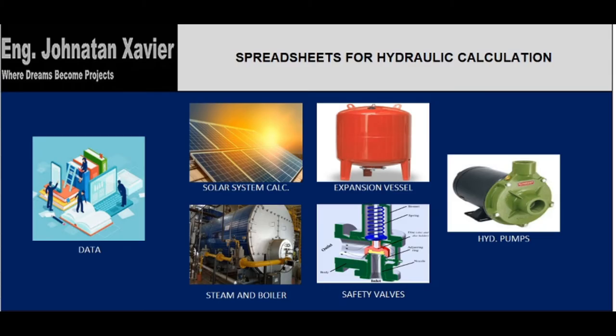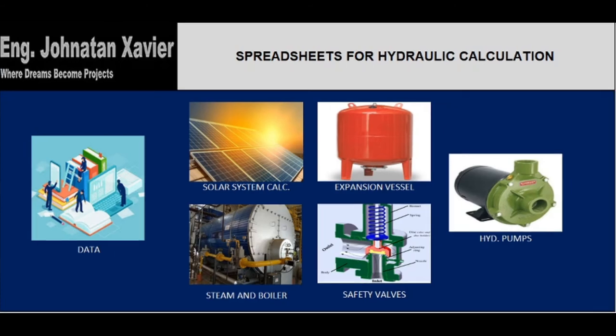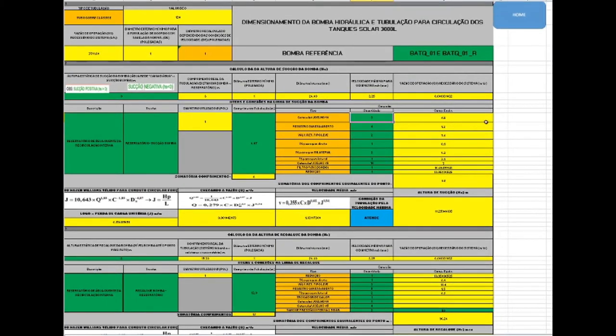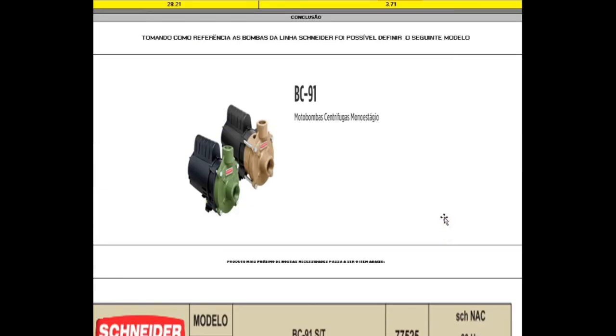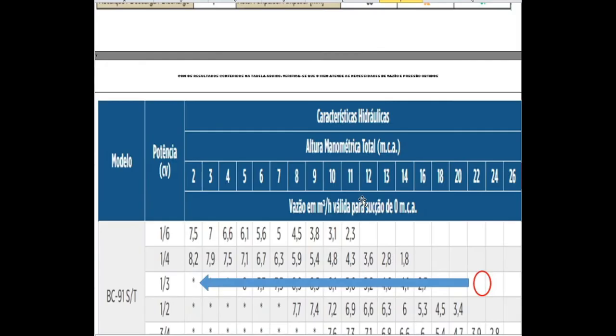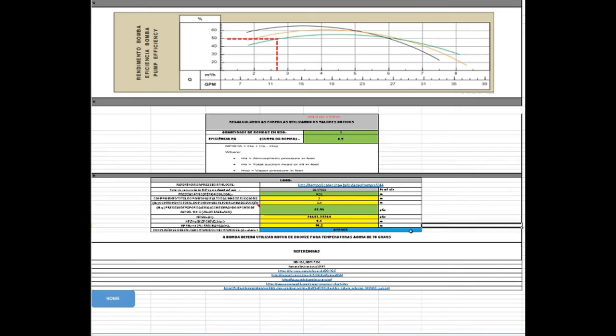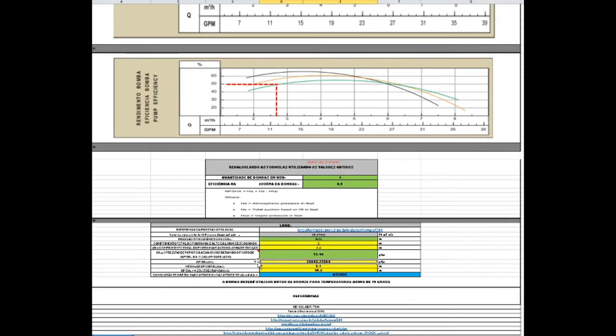Automatic spreadsheets are prepared to check calculations and the appropriated head losses, comparing with the manufacturer's pump curves according to the updated standards. Here, we can fill up all fittings and it will give me automatically all results according to standards and calculations, such as Hazen-Williams. At the end, I can get all pumps and its information. I also can see if it's suitable or not for my system, according to the head losses and NPSH available and NPSH required.